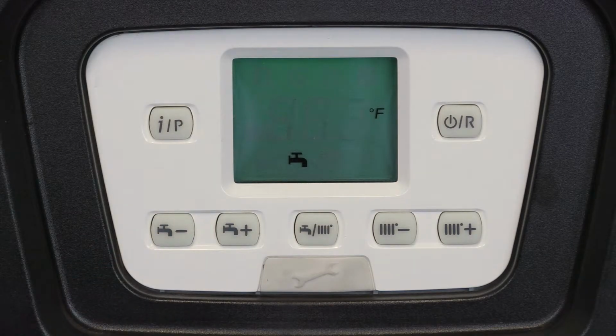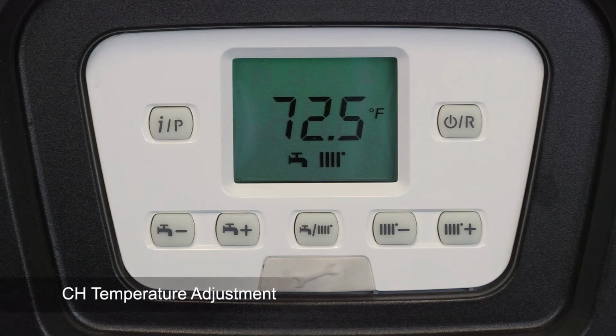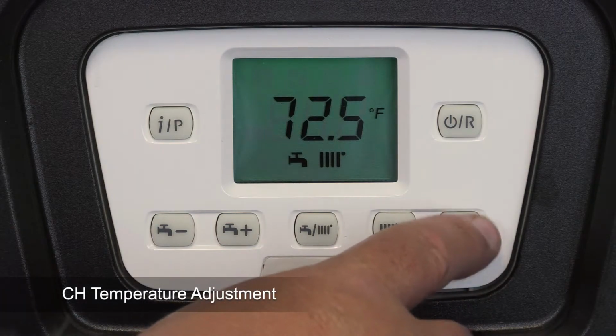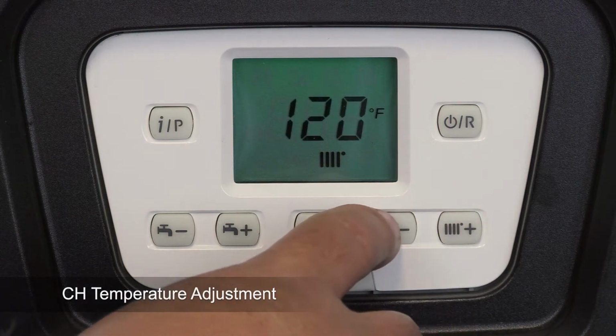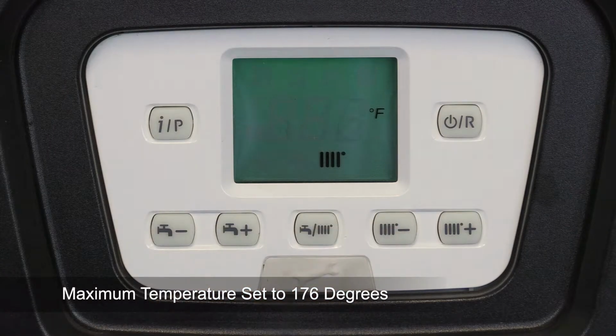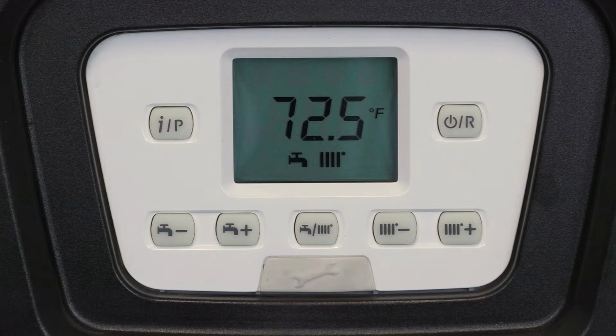To adjust your central heating supply temperature, use the plus and minus buttons with the radiator icon on them. The default max temperature for your heating loop is 176 degrees. This cannot be increased. You can decrease it to the temperature you need for the heating elements in your home. For example, if you have an air handler, you can turn it down to 140 degrees, or if you're using radiant floor heat, you can lower it to 120 degrees.